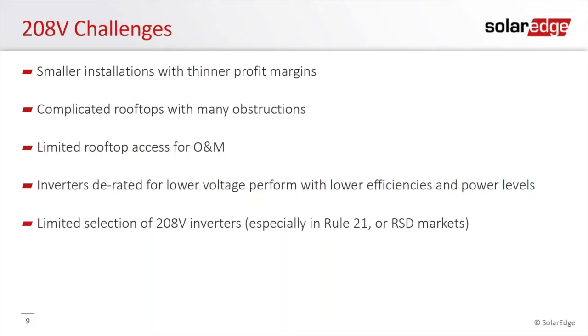A limited selection of 208 volt inverters. Not a lot of manufacturers really focus on this segment. They're focused at higher voltage levels or in residential, especially if you look at things like Rule 21. In California, we have Rule 21, a special certification, and not all inverters are certified to meet Rule 21 requirements, so your selection gets even smaller. If you're in rapid shutdown markets, how do you satisfy those requirements as well? These are some of the challenges that we've seen in the 208 volt segment.